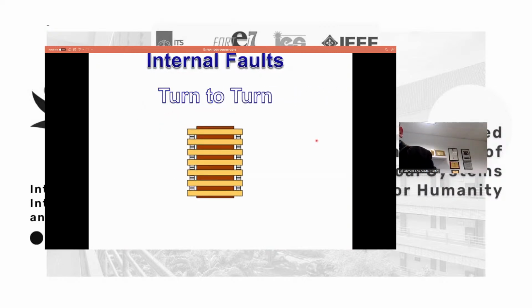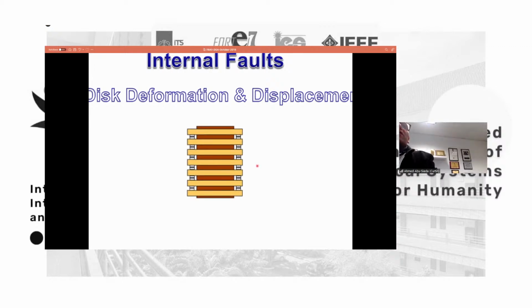We started this research by using finite element analysis, where you can emulate physical systems using this software. And we simulated turn-to-turn short circuit, like you can see in the animation here. We short-circuited some turns to create this. That can come from insulation deterioration inside the transformer. Disk deformation: because of the huge electromagnetic force that may be generated during faults, you may have deviation in the winding, the discs. We call it disc space variation or deformation.